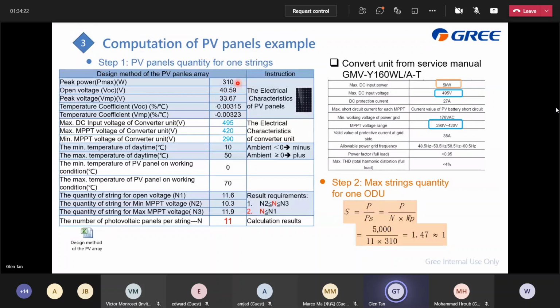The max DC power output you get from these PV panels. So you can get this 1.47, which we need to round down to only 1. That means for this model, the maximum you can connect is only one string, and for one string you can connect up to 11 panels.